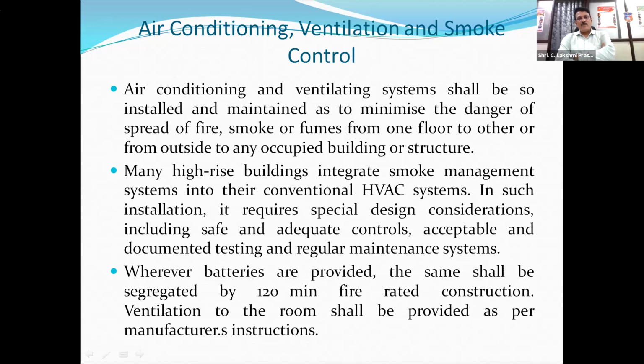And there has to be battery backup for these egress lighting, especially staircases, then corridors, then directional signs, all this lighting, exit signs, all should be with a battery backup of minimum 90 minutes, 1.5 hours. Then the HVAC systems, heat, ventilation, and air conditioning, because the majority of modern day buildings, other than residential, are provided with central air conditioning systems, and there are many safety systems that have to be incorporated in the HVAC systems, like fire dampers in the system, and having the air handling unit separately on every floor and with proper protection. And if batteries are used, then they should be segregated by minimum 120 minutes fire rated construction, and ventilation has to be provided to the room where the batteries are stored.